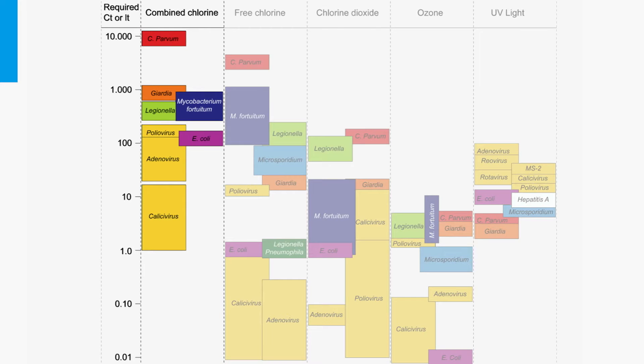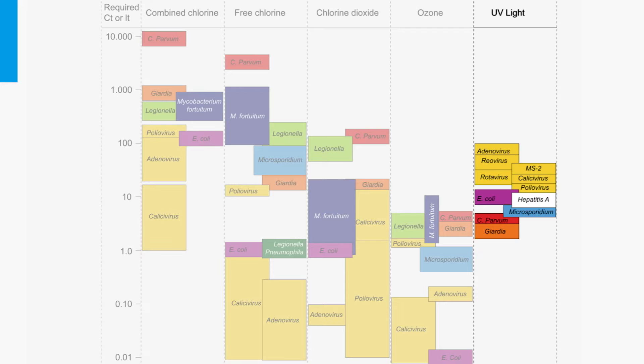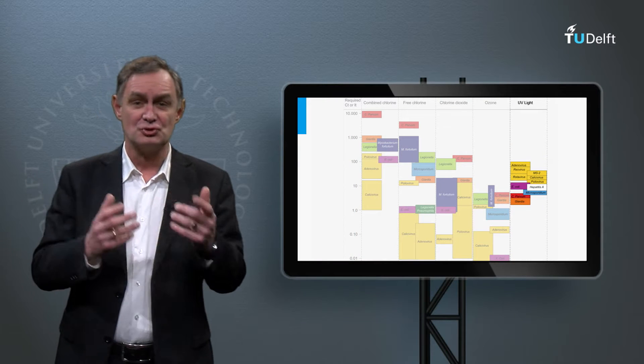If free or combined chlorine is used as disinfectant – which is formed when chlorine reacts with ammonia or organic nitrogen – a low CT value is required for viruses and E. coli, while for protozoa, Cryptosporidium parvum and Giardia, a high CT value is required. For UV radiation, it is the other way around: a higher IT value is required for viruses compared to protozoa.